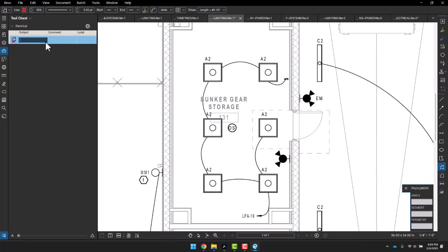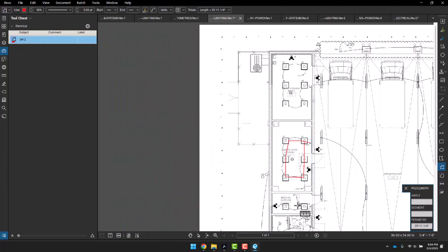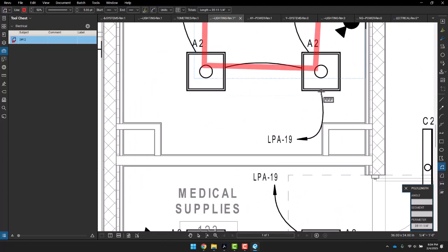They didn't specify how many conductors. So normally we use 3 number 12, which means 3 conductors. That is the typical conductor for a circuit. Okay, so I'm gonna click here, here, here, here, here. The reason I use number 12 over here is because this one is relatively short, so I'm gonna use number 12. And then you can click here.